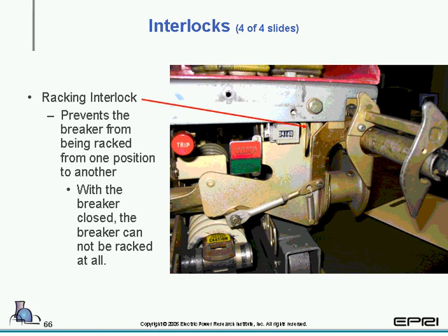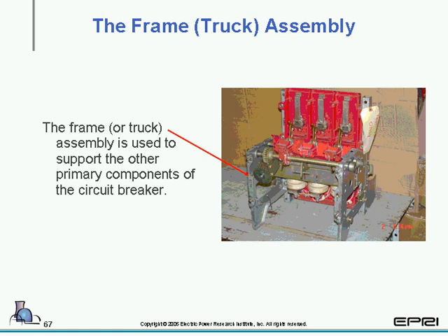The last one we're going to take a look at is a racking interlock, which prevents the breaker from being racked from one position to another. With the breaker closed, the breaker cannot be racked at all. And you'll see our arrow actually points to this piece of metal. As the breaker goes closed, this particular small piece of metal will be pushed out and actually block the racking cam from moving to the side, preventing the breaker from being racked. And that pretty much concludes the basic interlocks.